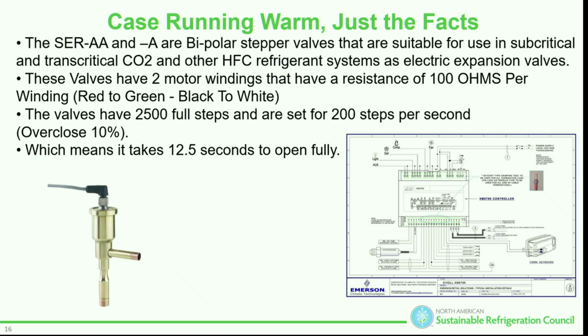Except for the fact that we have a 10% overclosure. What does that mean? That means in order to make sure that valve finds its way home, to make sure it's fully seated, we close an additional 10%, and I'm not good at math, but I think that's 250 additional steps to make sure that is programmed properly as well.